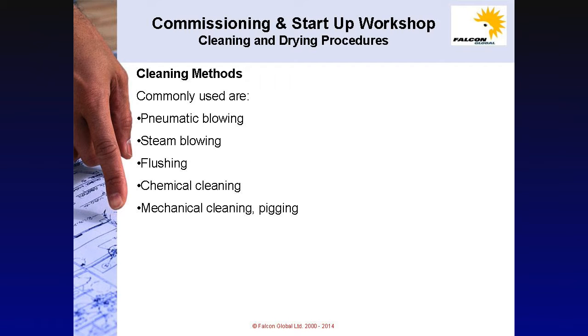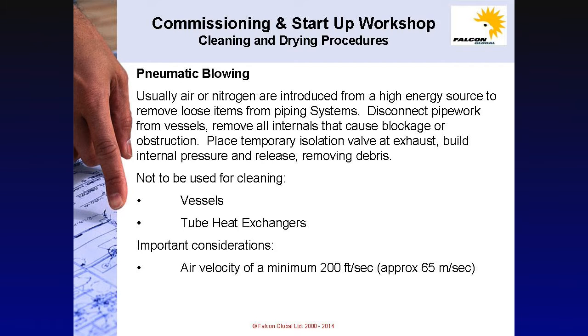Cleaning methods commonly used are pneumatic blowing, steam blowing, flushing, chemical cleaning, mechanical cleaning and pipeline pigging. Pneumatic blowing. This is usually air or nitrogen and is introduced from a high energy source to remove loose items from piping systems. The normal procedure is to disconnect piping from vessels, removing all internals that could cause blockage or obstruction. Place a temporary isolation valve at the exhaust, build the internal pressure and release, removing the debris. Note, this is not to be used for cleaning vessels or tube heat exchangers. Important considerations are an air velocity with a minimum of 200 feet per second, around about 65 meters per second.